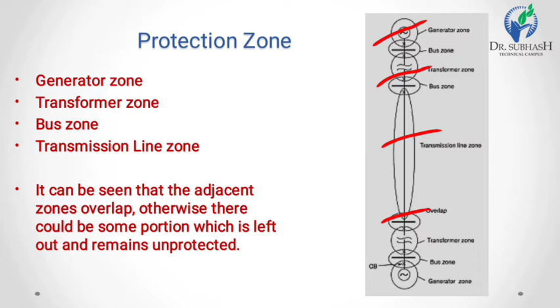As you see, some parts of the lines overlap, which means no part is left unprotected. The various protective zones of a typical power system are given in the figure, like generator zone, transformer zone, bus zone, transmission line zone. As you see in the figure, overlapping between the adjacent zones is unavoidable. If a fault occurs in the overlapping zone, in a properly protected scheme, more circuit breakers than the minimum necessary to isolate the faulty element of the system would trip. A relatively low extent of overlap reduces the probability of faults in this region, and consequently tripping of too many breakers does not occur frequently.